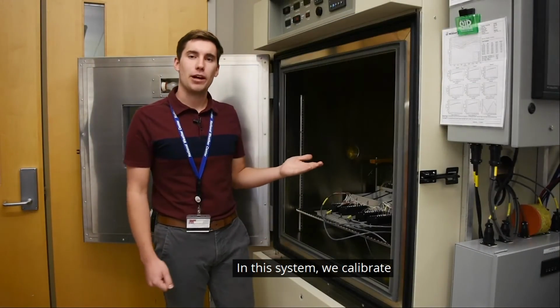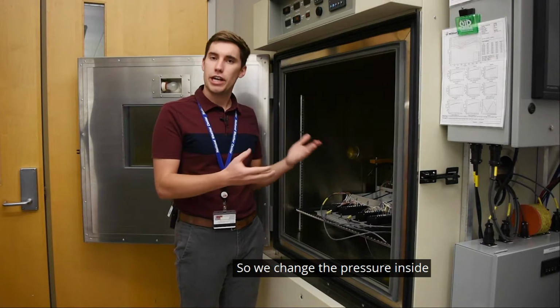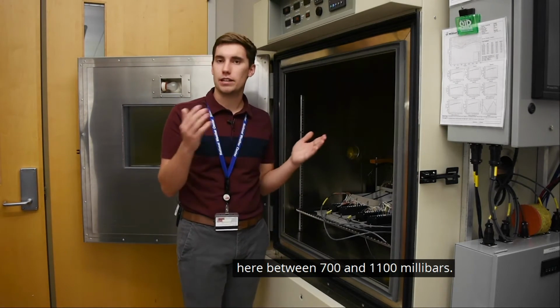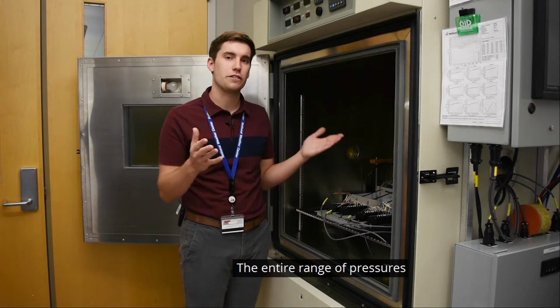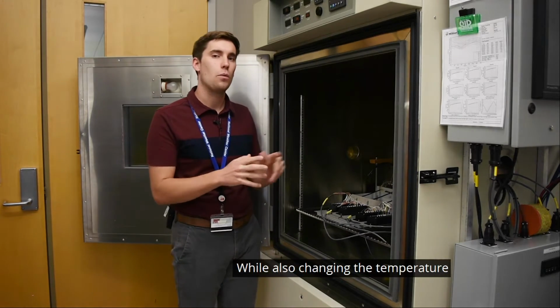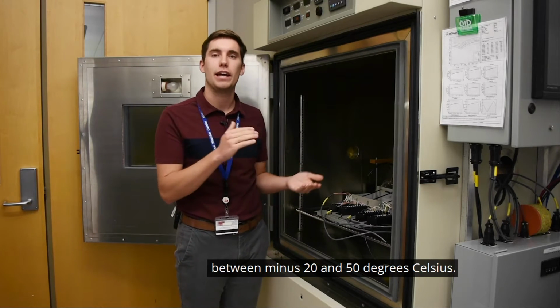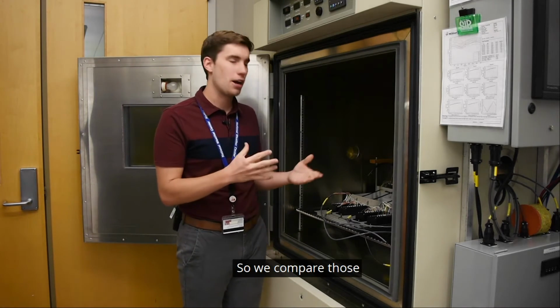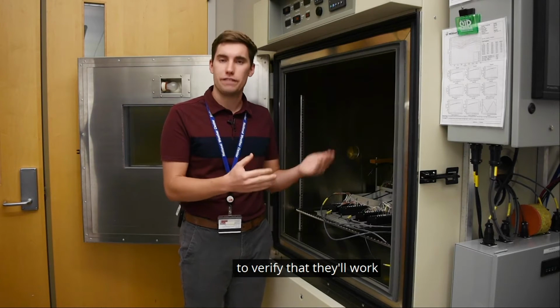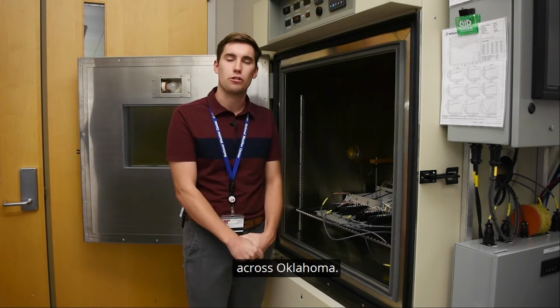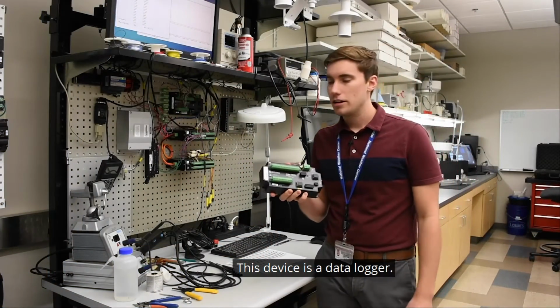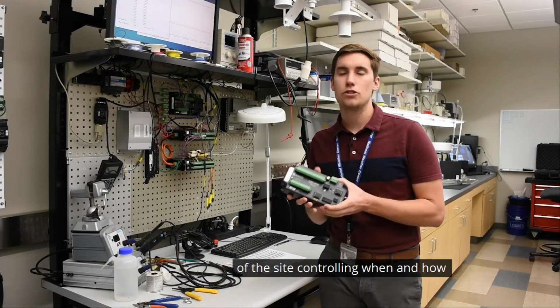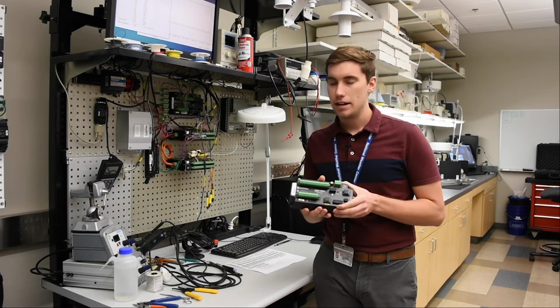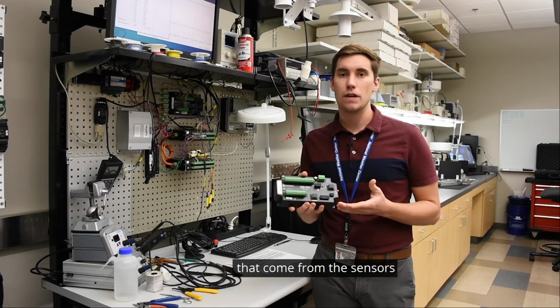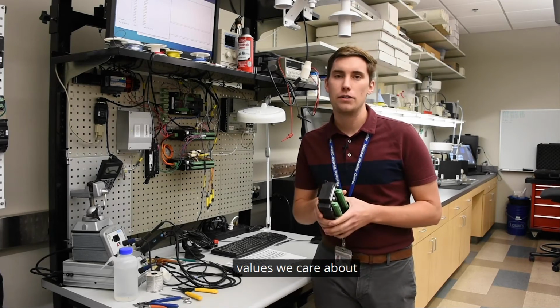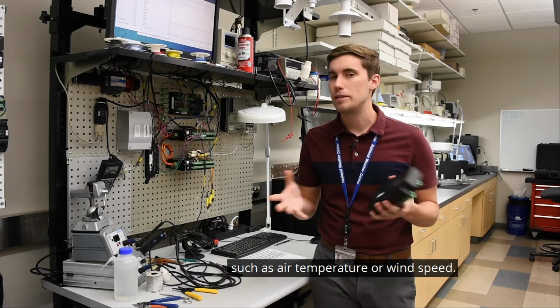In this system, we calibrate the Oklahoma Mesonet barometers. So we change the pressure inside here between 700 and 1100 millibars, the entire range of pressures that barometer could experience, while also changing the temperature between -20 and 50 degrees Celsius. So we compare those barometers against a reference to verify that they'll work during weather conditions across Oklahoma. This device is a data logger. It kind of acts as the brain of the site, controlling when and how each measurement is taken. It interprets the electrical signals that come from the sensors and translates them into values we care about, such as air temperature or wind speed.